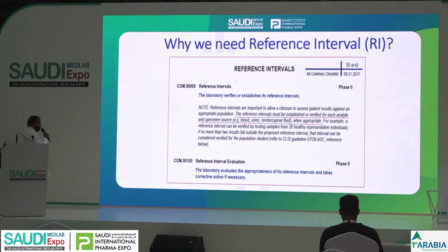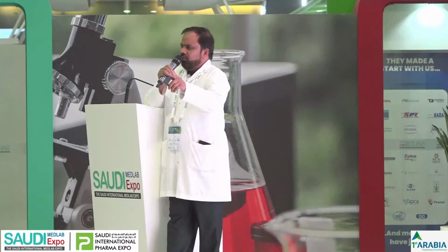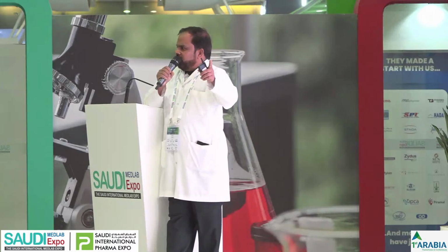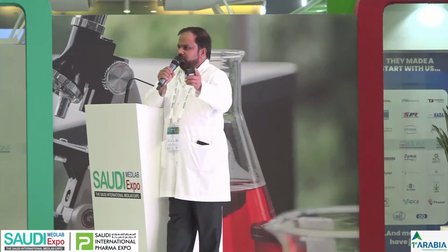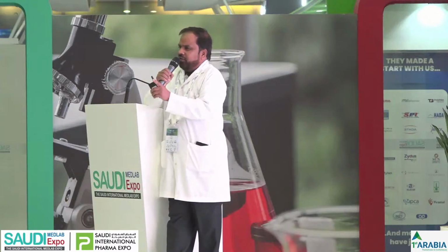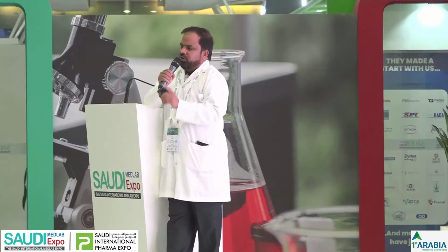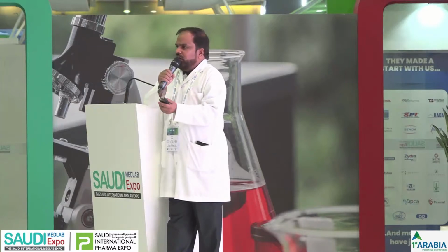So let's see what the CAP is saying. The CAP is saying that the reference interval must be established before you verify the result. If you are using one kit for serum, for whole blood, for urine, for CSF, for any biological sample, all of them should be validated separately. Linearity should be done separately. Comparison should be done separately. Reference interval should be done individually for each sample type, regardless of the kit and regardless of the analyzer. All of them have to be done. So there is no way to leave this as it is.